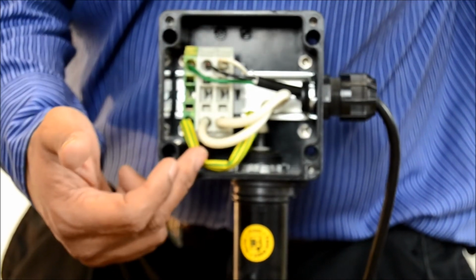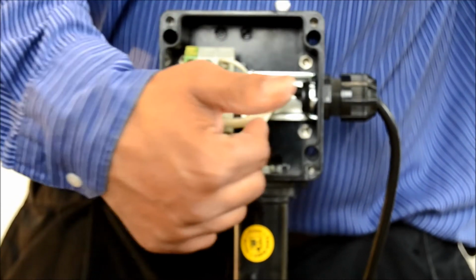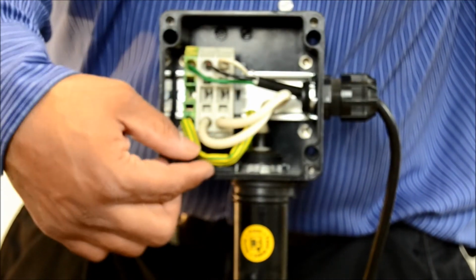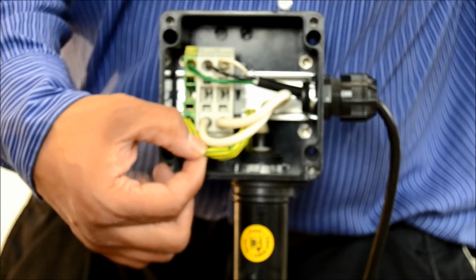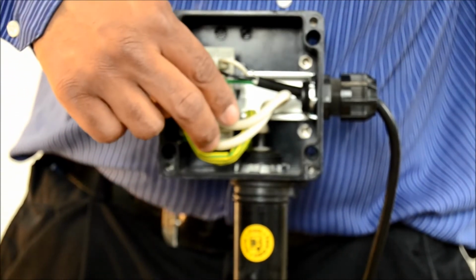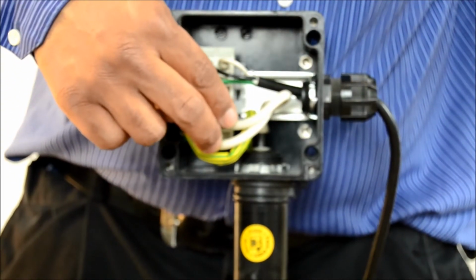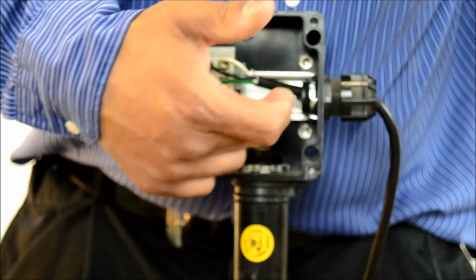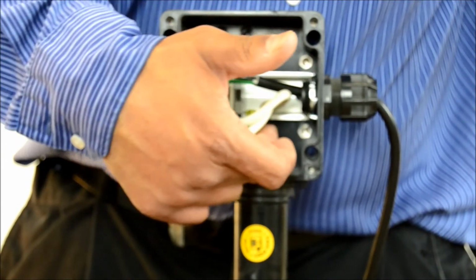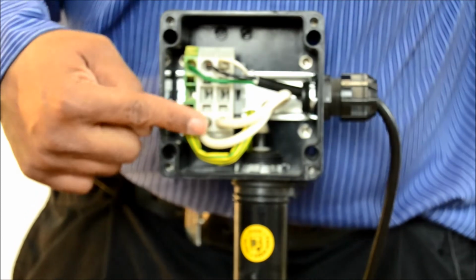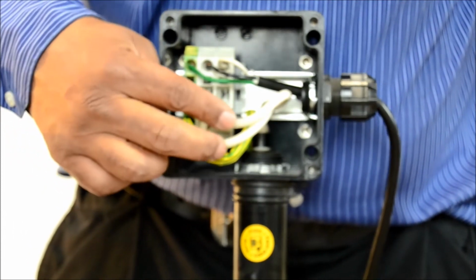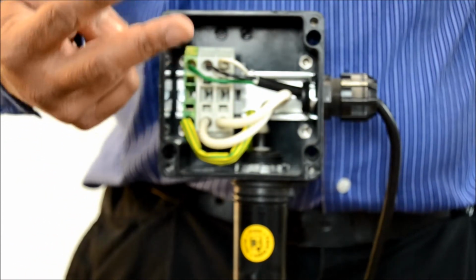Then, on the other side, you have a transition into the heat trace. Now, this is your ground braid here from your heat trace, and then these are your two bus wires. These go to your two bus wires. You need a transitional piece, which is a core seal. So this is what this is right here, and essentially it helps for two reasons.